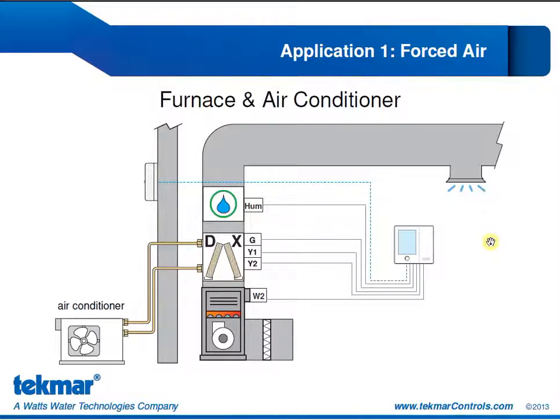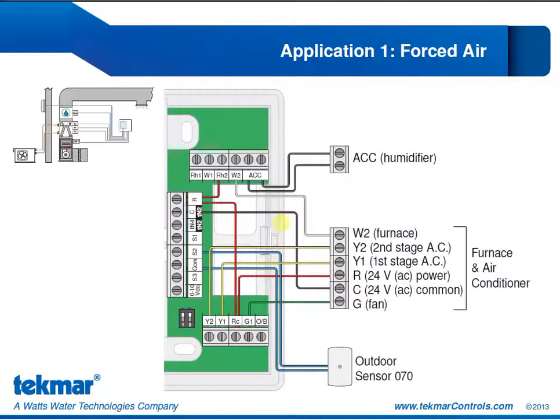We're going to jump now to our applications. Application number 1 is our forced air application with traditional heat-cool equipment. We have a single stage of heat being provided by our furnace, and that's being controlled through the W2 relay. When we're in cooling, we have up to 2 stages of cooling provided by our air conditioner, controlled through the Y1 and Y2 relays. Of course, we need the fan to operate, controlled through the G relay. You can also see a humidifier in the ductwork. It says HUM here, just to represent that this is a humidifier. It's actually controlled through the accessory relay.